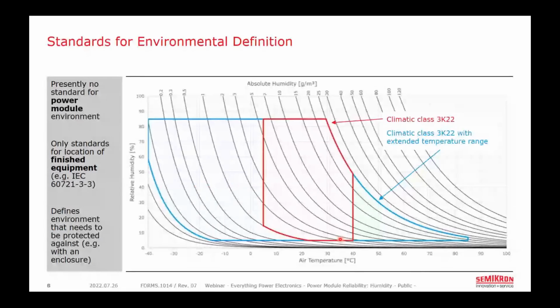For example, if a power converter can withstand a 3K22 climatic class, you can see here that it is designed to operate in a relative humidity from 5% up to 85% relative humidity, and from temperatures from 5 degrees Celsius up to 40 degrees Celsius. And so that would mean that whatever electrical enclosure you're putting around that electronics needs to be designed such that all of the electronics inside can survive if the external environment falls within this red boundary.